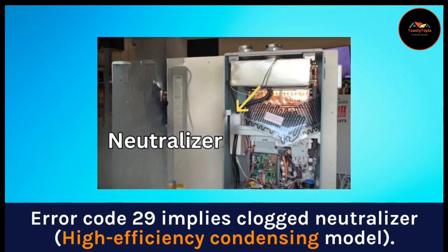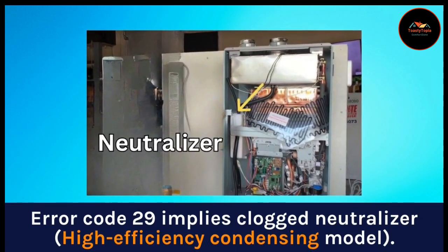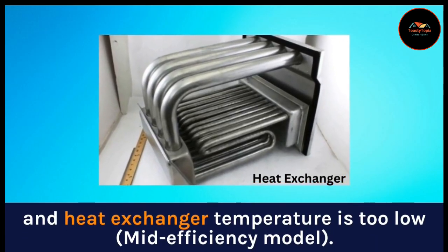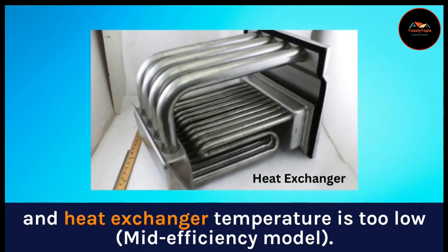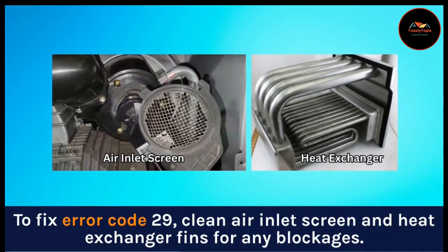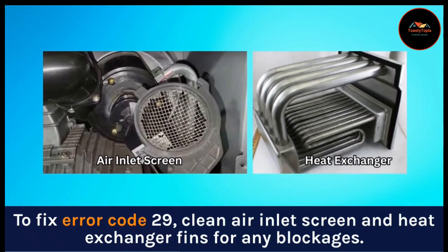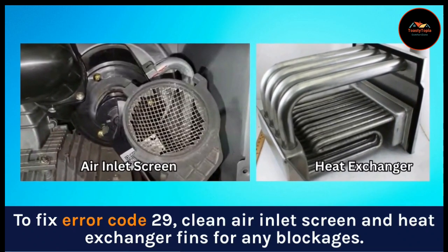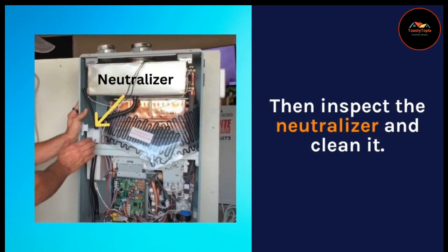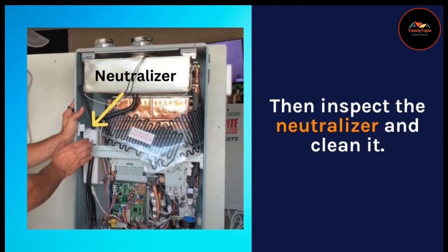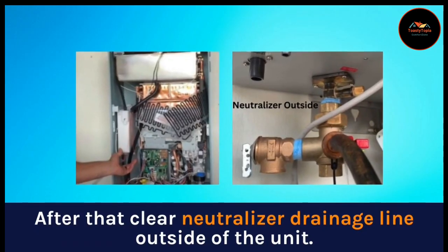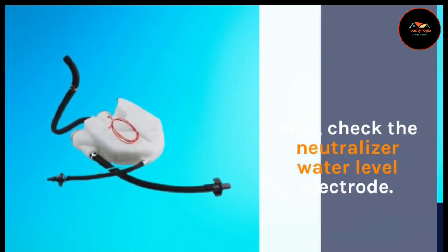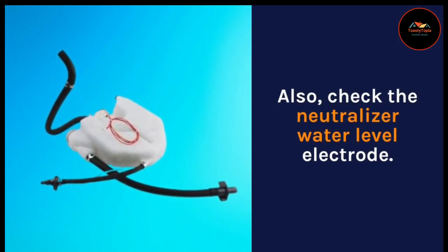Error code 29 implies a clogged neutralizer on the high-efficiency condensing model, and heat exchanger temperature too low on the mid-efficiency model. To fix error code 29, clean the air inlet screen and heat exchanger fins for any blockages. Then inspect and clean the neutralizer, clear the neutralizer drainage line outside the unit, and check the neutralizer water level electrode.